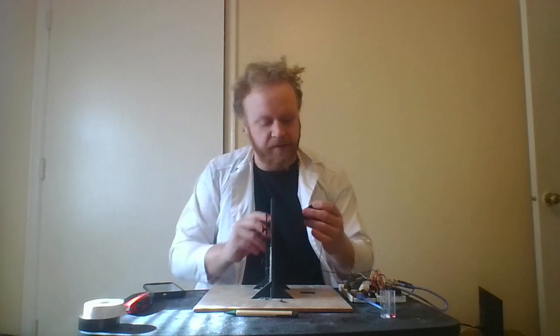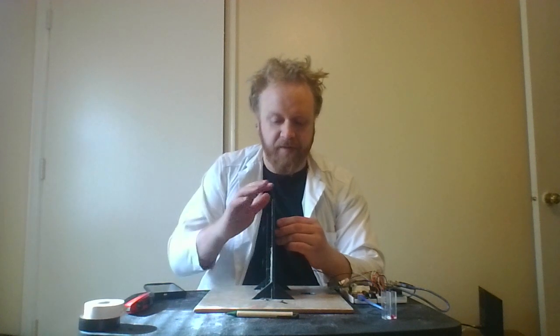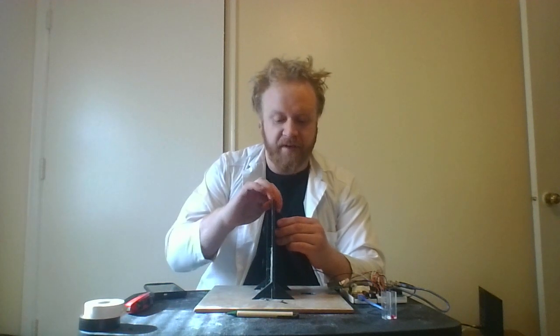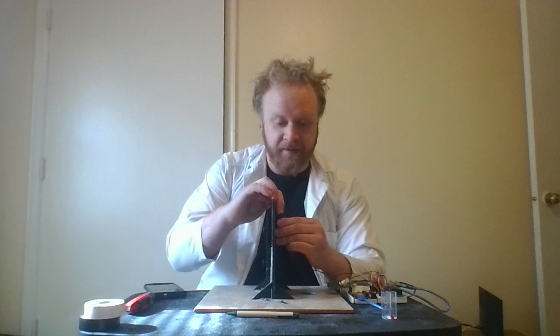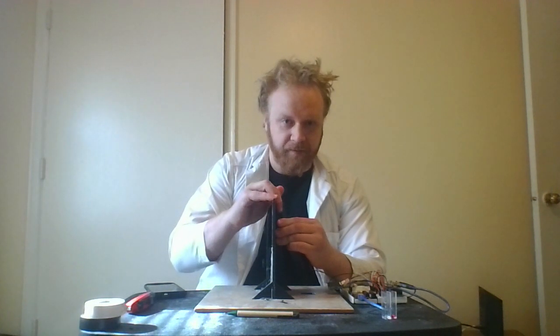Then this piece here also just slips on. There's actually little recesses in place for it to slide into. This is again to prevent stray light. As I mentioned during the main video, the stray light is the absolute bane of all spectroscopy. Any light that's not coming from your incident source, not passing through your sample, can then cause trouble at your final end result.